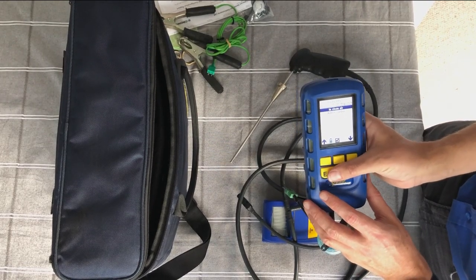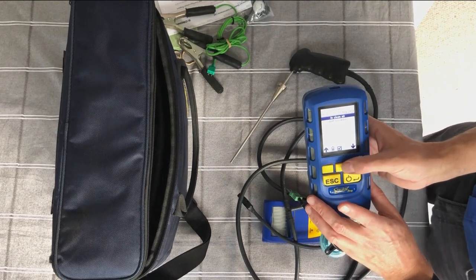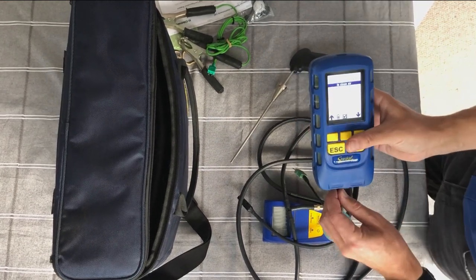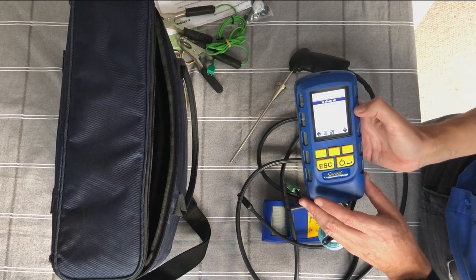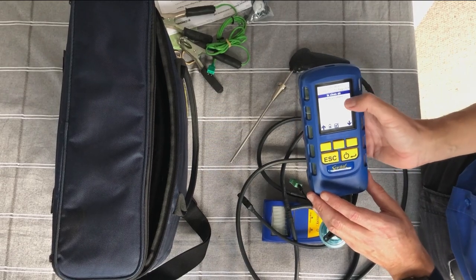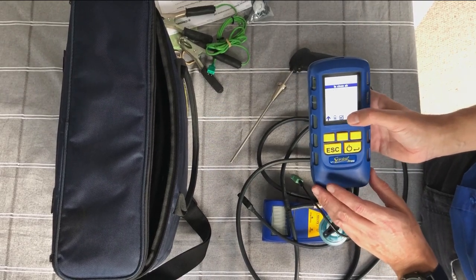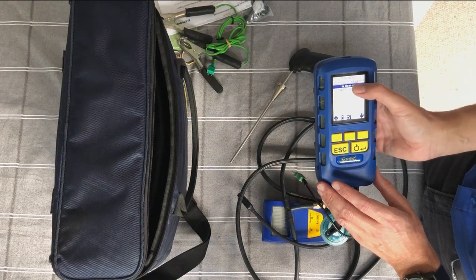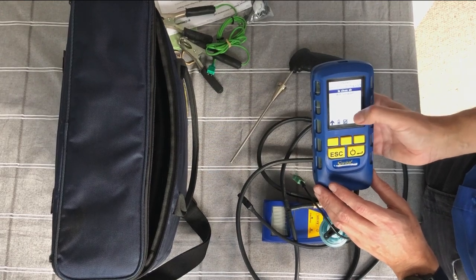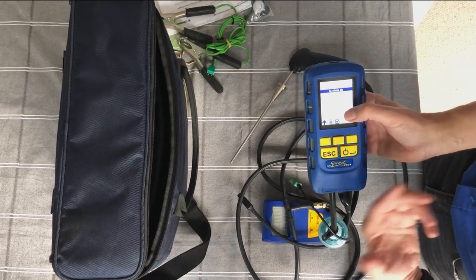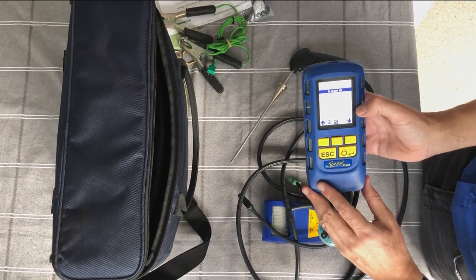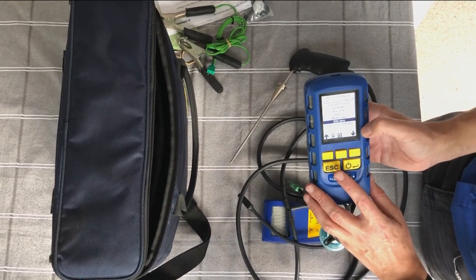CO2 zero. Okay, that's a bit specialist, but that's if you've got a CO2 monitor for doing ambient CO2, so commercial catering and things like that. You can zero it in fresh air, i.e. 400 ppm, because that's what's in ambient CO2 in air. Or if you've got a scrubber, you can zero it to zero because the scrubber takes out the CO2. Bit of an irrelevance for most people.